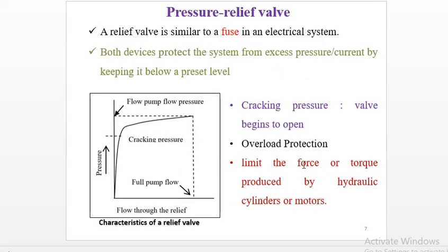If you talk about the cracking pressure or the characteristics of the pressure relief valve, a relief valve is similar to a fuse in an electric system. As the cracking pressure is reached, it will allow the flow to the reservoir. Both devices protect the system from excess pressure, or excess current in an electric system, by keeping it below a preset level. So cracking pressure is the pressure at which the valve begins to open.